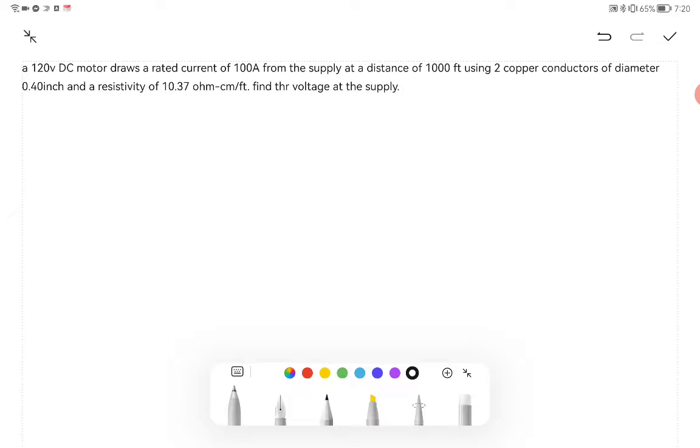So first we will write our given values. We are given the voltage of 120V, a current of 100 ampere, and a distance of 1000 feet. But we are using two copper conductors so it will be multiplied by two, giving us 2000 feet.